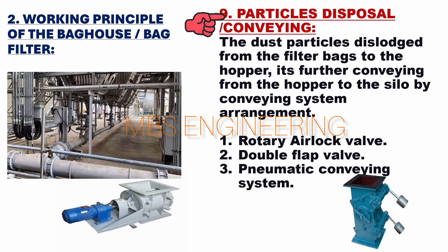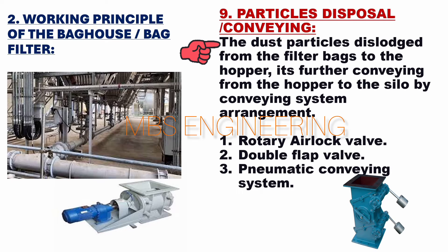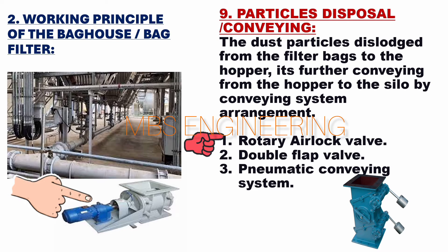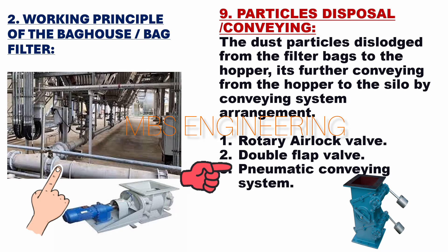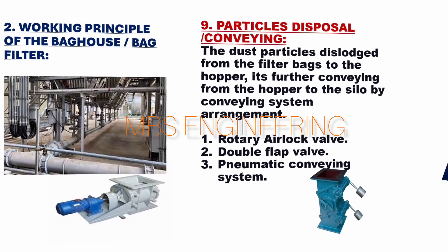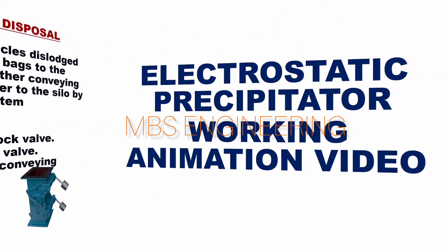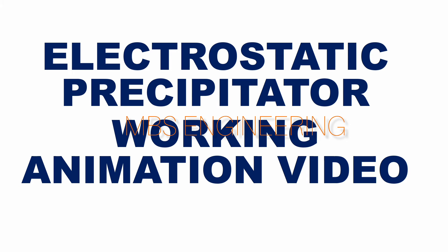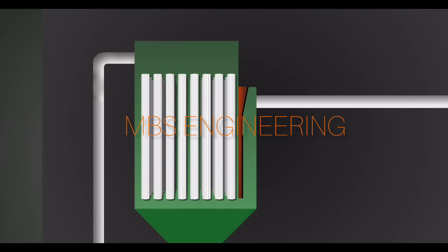Step 9 — Particle Disposal and Conveying: The dust particles are dislodged from the filter bags to the hopper and further conveyed from the hopper to the silo by the conveying system. The dust disposal arrangements used for the bag house system include: the rotary air lock valve, the double flap valve, and the pneumatic conveying system. Please refer to the pulse jet bag house working animation video for better understanding.